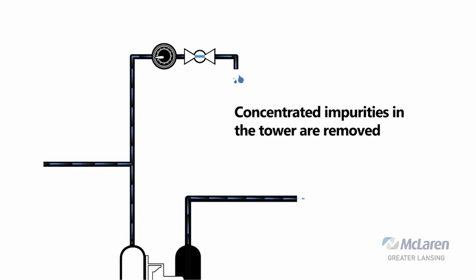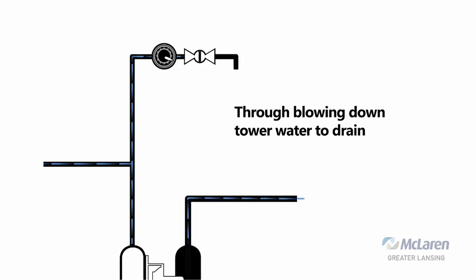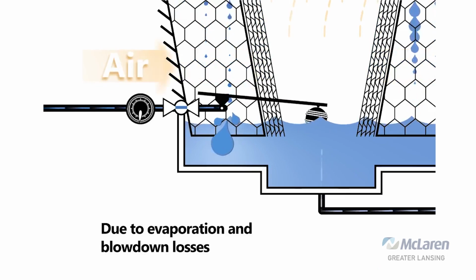In your case, it's equipped with a motorized ball valve, and so it's set up to blow down for about 20 seconds every 12 hours. There's nothing to do here except occasionally grease motor bearings. So we want to keep the velocity up to drive the solids. The solids end up going this way. There's a plate down here, and the solids ultimately drop out down here, and that's where they collect until it gets purged. The clean water comes right back up through the center, and it's pretty cool to see.